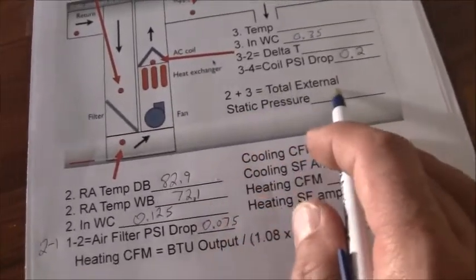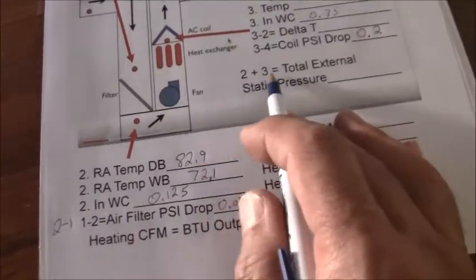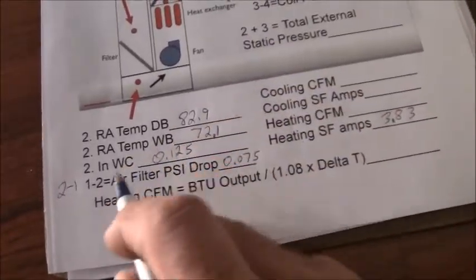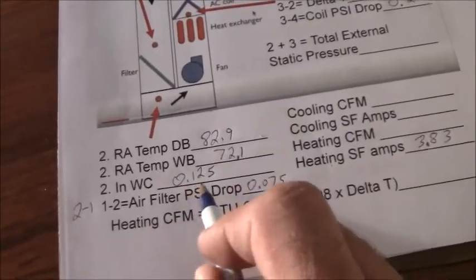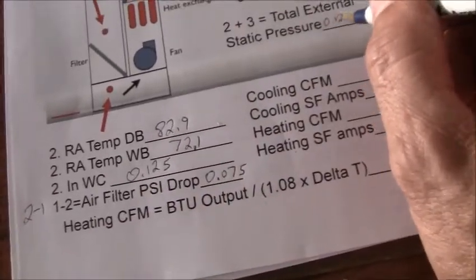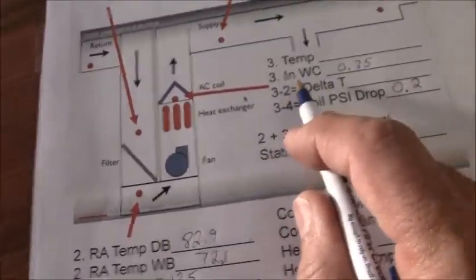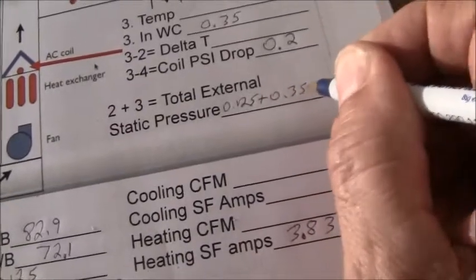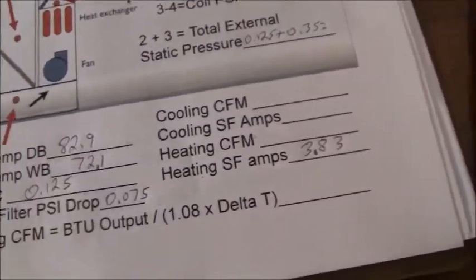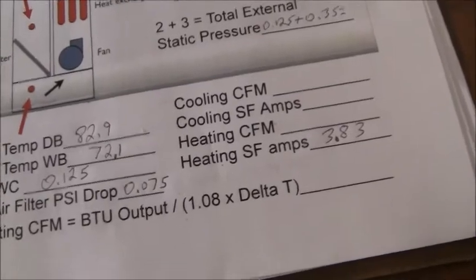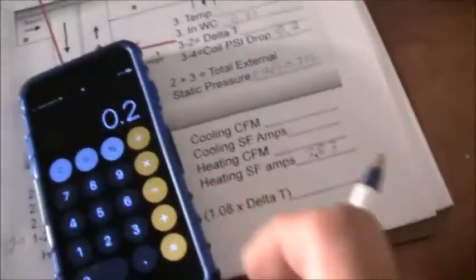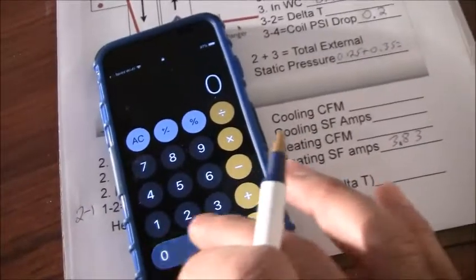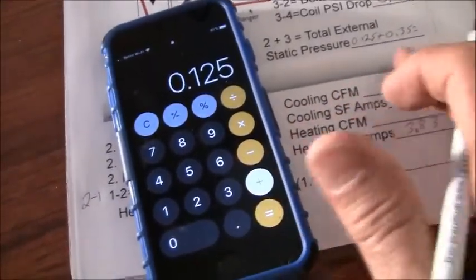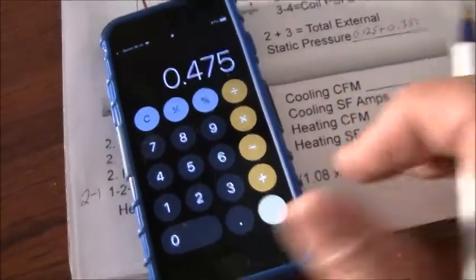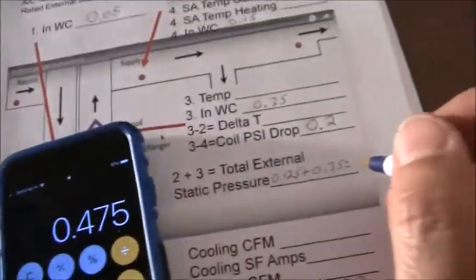Okay, now that we know that, we can figure out a few more things. Now we do want to know the total external static pressure. That's going to be 2 plus 3. So 2 is 0.125 plus 3, which is 0.35. Okay, let's go ahead and get that going. 0.125 plus 0.35 equals 0.475.